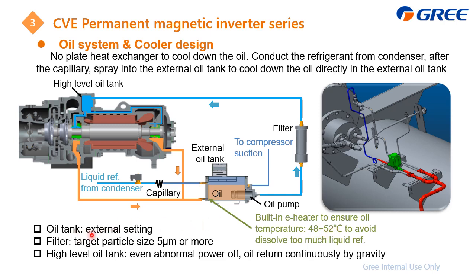Also, compared with the CE series, the oil tank here is externally set, and for this filter, the target particle size lower limit is 5 μm. We also have a high level oil tank, just in case of a sudden power failure, so the oil can flow into the gear for lubrication by gravity automatically.